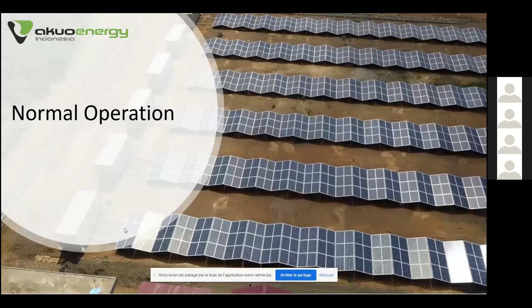We used an SDMO genset here, as you could see from site. As mentioned earlier, one of the requirements was for the power plant and systems to be designed for year 20, to make sure there's no shortage of power just before the population gets used to it and starts developing activities. Because of this oversizing, for the first few years the system is oversized and the genset is little used, since it's sized assuming a larger demand designed for year 20.